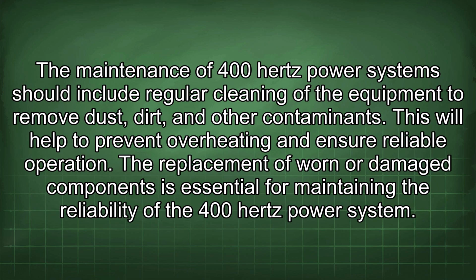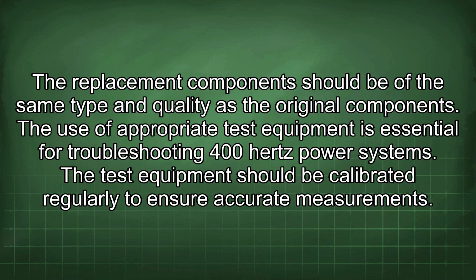The maintenance of 400 Hz power systems should include regular cleaning of the equipment to remove dust, dirt, and other contaminants. This will help to prevent overheating and ensure reliable operation. The replacement of worn or damaged components is essential for maintaining the reliability of the 400 Hz power system. The replacement components should be of the same type and quality as the original components. The use of appropriate test equipment is essential for troubleshooting 400 Hz power systems. The test equipment should be calibrated regularly to ensure accurate measurements.